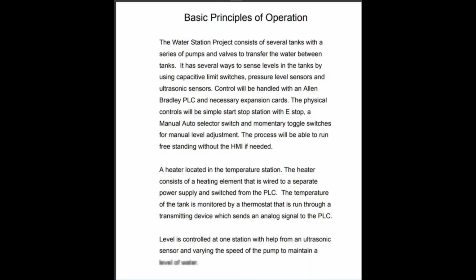A heater located in the temperature station. The heater consists of a heating element that is wired to a separate power supply and switched on from the PLC. The temperature of the tank is monitored by a thermostat that is run through a transmitting device which sends an analog signal to the PLC. Level is controlled at one station with help from an ultrasonic sensor, and varying the speed of the pump to maintain a level of water.